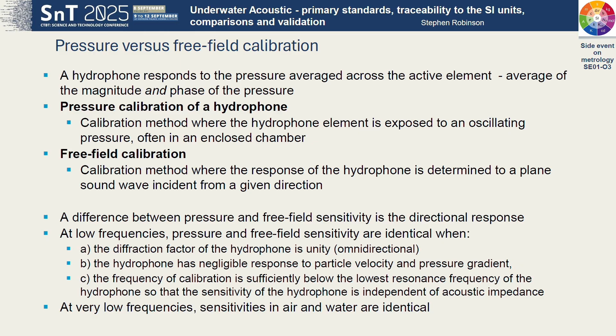And the pressure calibration is equivalent to a free field calibration, so long as the hydrophone is small and acoustically hard at low frequency, so you're much smaller than the acoustic wavelength, and as long as it doesn't respond to pressure gradient or sound particle velocity, then you've got essentially a sensitivity that's equivalent to the free field. And because it doesn't sense the medium impedance at these very low frequencies, it's actually the same sensitivity in air as in water. So we can do a calibration in air, which is equivalent to water at these frequencies.